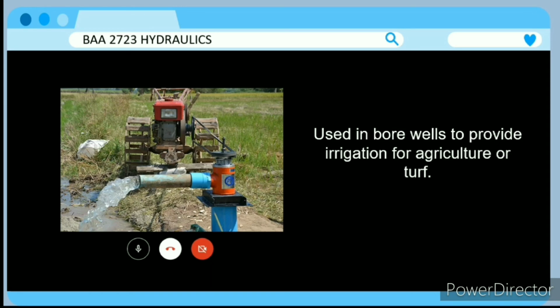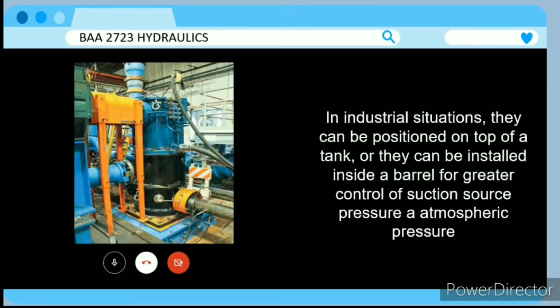The application of the vertical turbine pump is not only for bore wells, but it can also be used in an open channel such as a reservoir, river, or pump intake structure. In industrial situations, they can be positioned on top of a tank, or they can be installed inside a barrel for greater control of suction source pressure versus atmospheric pressure.